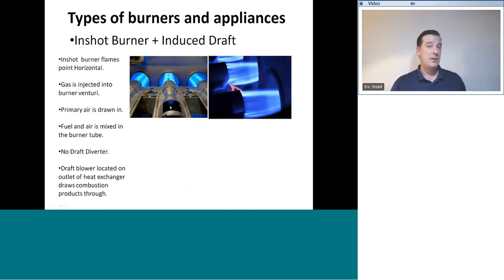Now, it's a common misconception that the draft inducer, which is pulling the combustion products through the furnace, also pulls in the primary air. It does not pull in primary air. Primary air is still drawn in through the Venturi effect because of the gas being injected down the burner in this direction. So if there is a primary fuel mixture issue, it is most usually going to be a gas pressure issue. The pressure of the gas causes the air to be drawn in. The more gas is pushed in, the more air is drawn in. The less gas is pushed in, the less air is drawn in.